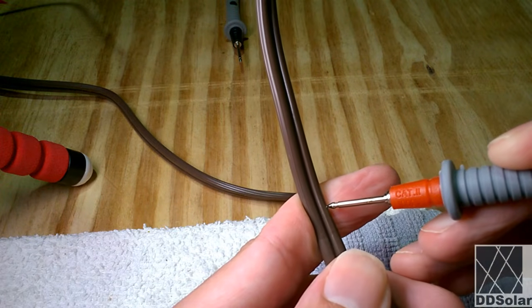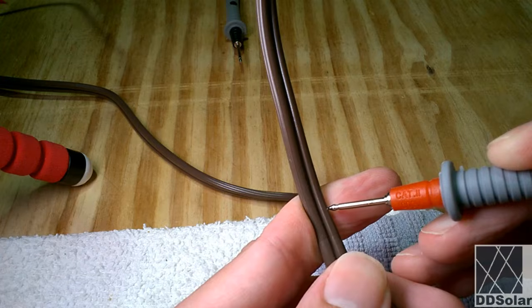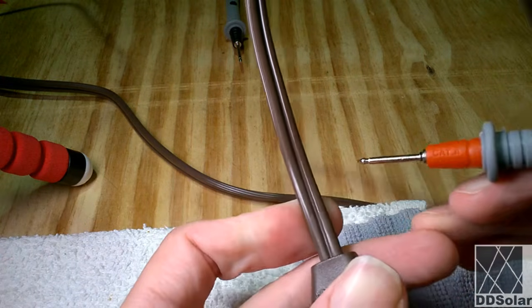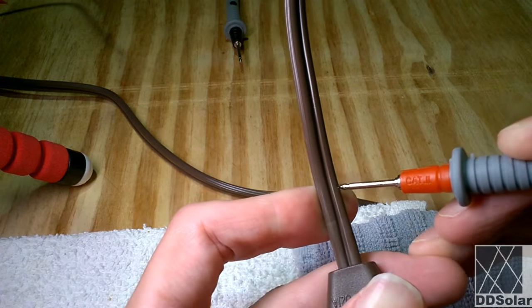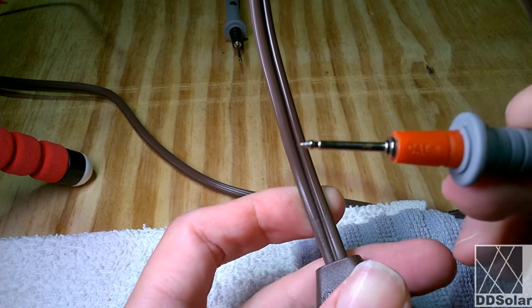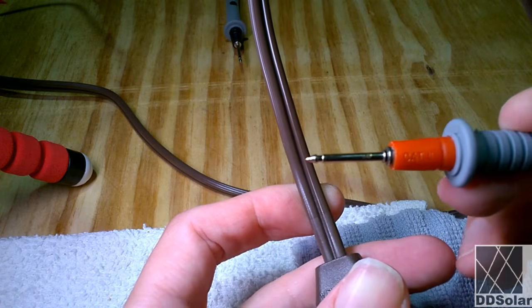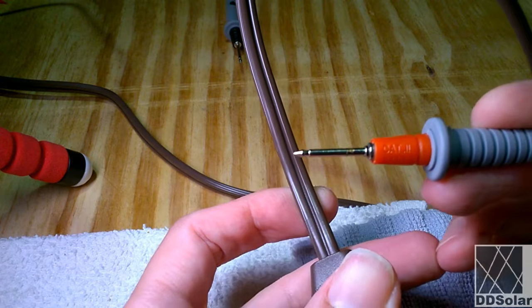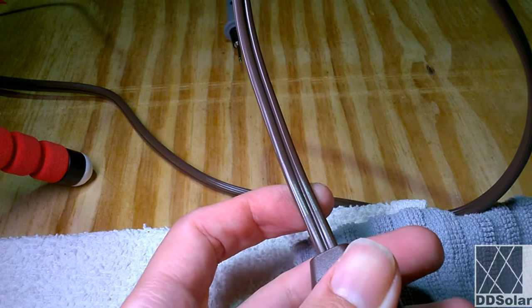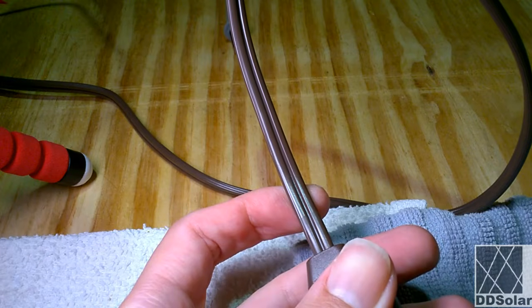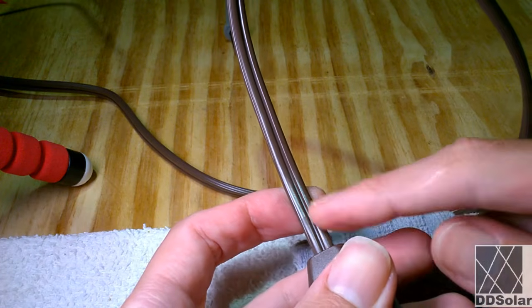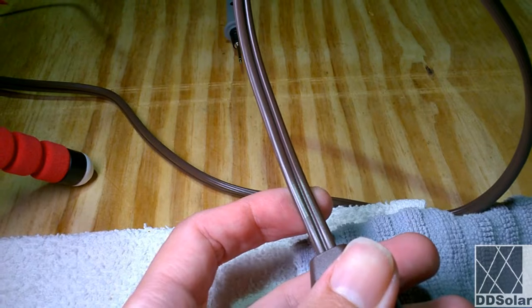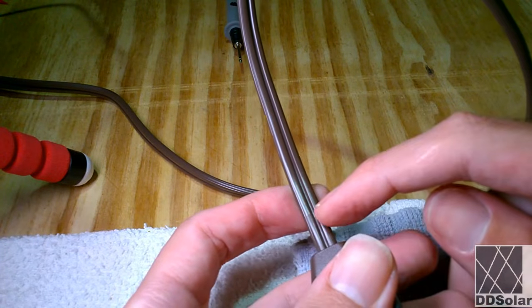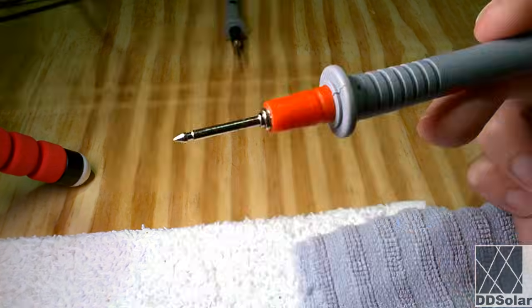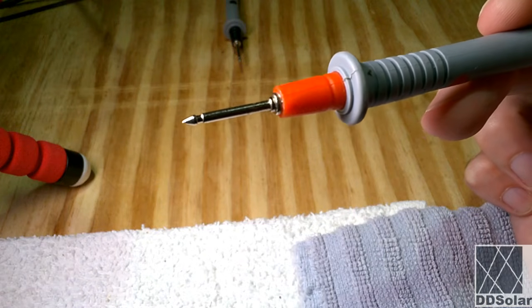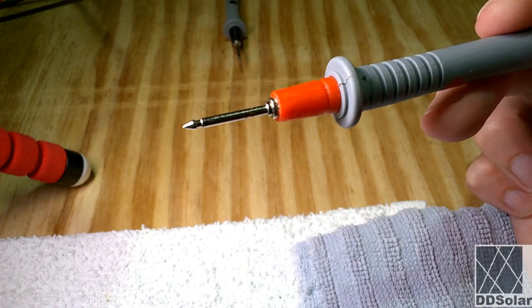I generally avoid doing this because I don't want to damage the insulation on my wire, but in some cases, in desperate situations, you may be forced to push through the insulation jacket of a wire, use the sharp point of the probe to get a voltage reading of a wire that is live and in circuit. This is mainly an FYI. I don't necessarily recommend doing it, and it's generally only for advanced users of multimeters. And keep in mind you are damaging the jacket or the insulation of the wire, and I would not want to really use an extension cord that had a hole poked in the insulation for any reason whatsoever. Another reason for the very pointy end of the probe is actually so that you can get a good connection.